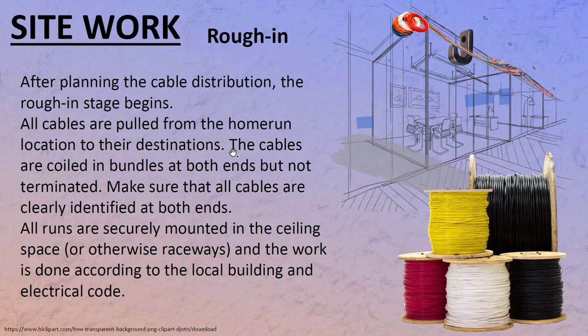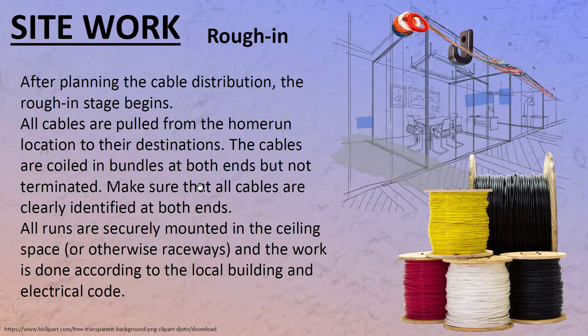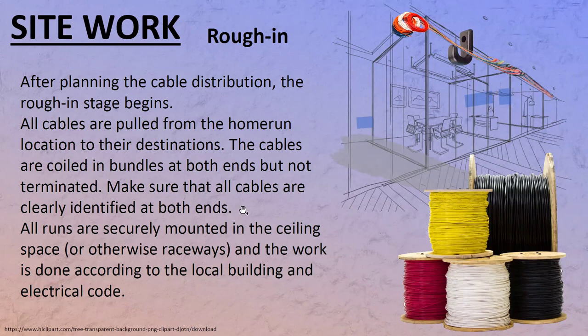Bill the client after all the wires are roughed in — another stage billed. In the rough-in stage, all cables are pulled from the home run location to their destinations, coiled in bundles at both ends but not terminated. Make sure all cables are clearly identified at both ends — just like we practiced in the patch panel lab, labeling cables at both ends. All runs are securely mounted in the ceiling space or raceways, and work must comply with local building and electrical code.